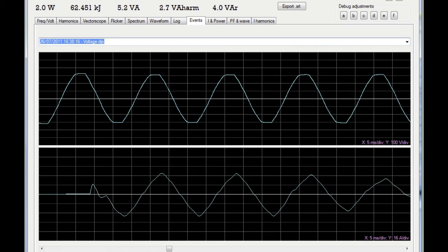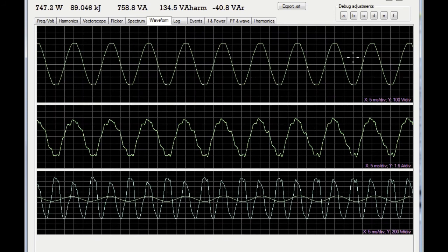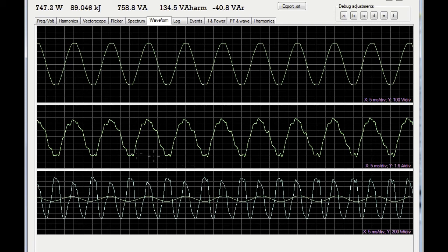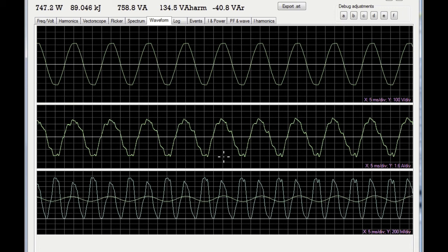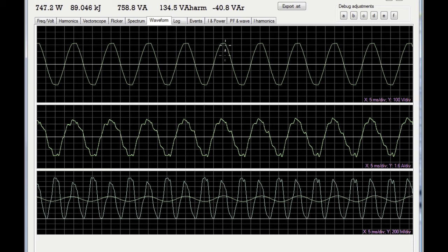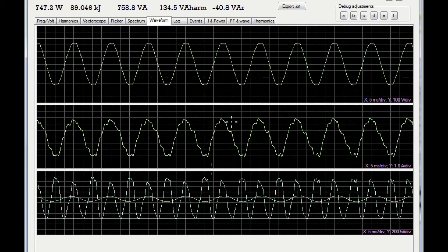What happens to these waveforms once the machine's stabilised? Let's look at the AC once it's reached stabilised level. Voltage waveforms, then current waveform. This is a much bigger scale. As you can see, 1.6 amps per division instead of 16 amps per division. You can see that the waveform is very distorted. It's got this lumpy appearance to it. Presumably, that's related to not just the fact that it's an AC induction motor, but there's probably some power factor correction capacitors in there as well. Power factor correction capacitors will draw a very distorted current if there is any distortion whatsoever in this voltage waveform. This should be a perfect sine wave. As you can see, these peaks are a bit flattened. That will cause considerable distortion of the current waveform if there is a capacitor present. So I suspect that's the reason for it.